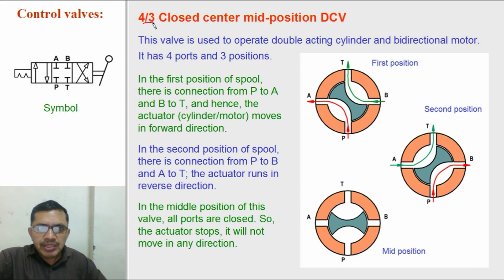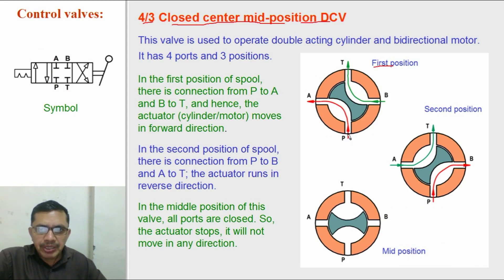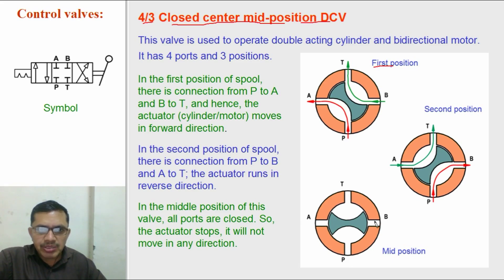This is the four by three closed center mid position direction control valve, but it is of the rotary spool type. In the first position there is connection from P to A and B to T. In the second position there is connection from P to B and A to T. In the middle position all ports are closed — P is closed, T is closed, and A and B are closed.